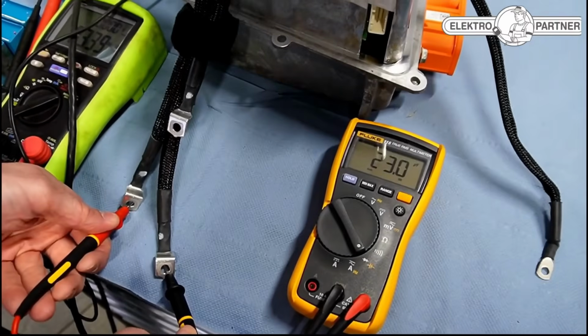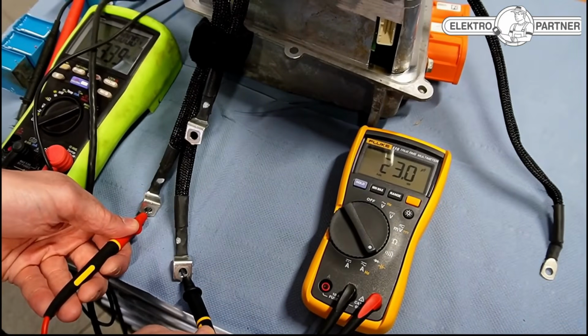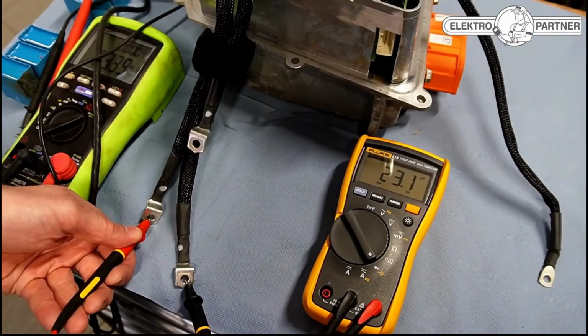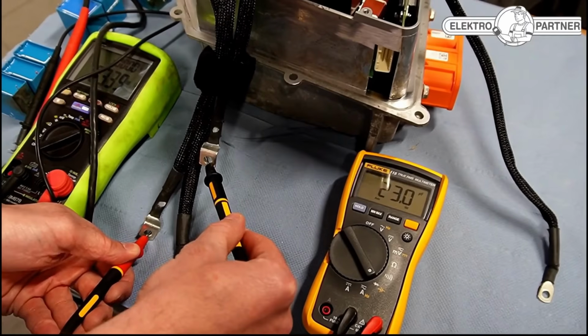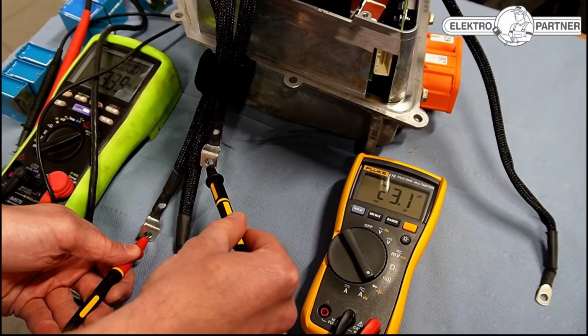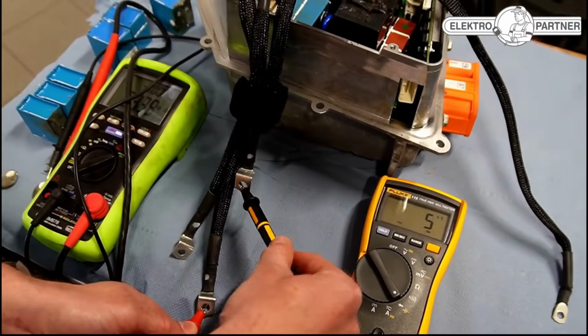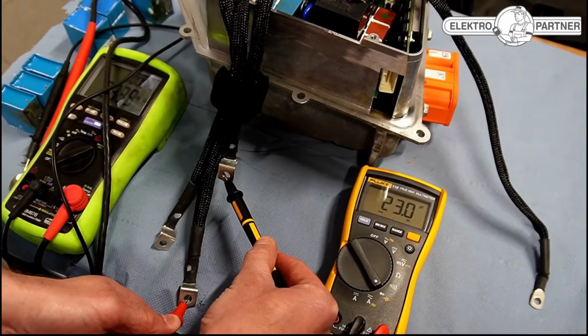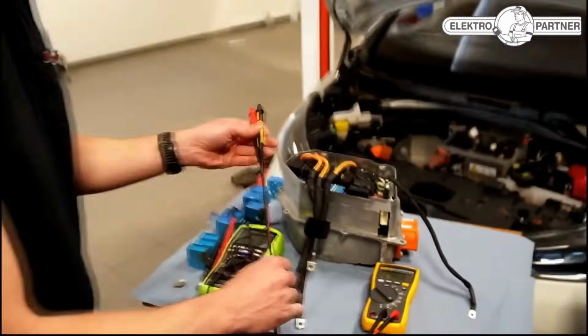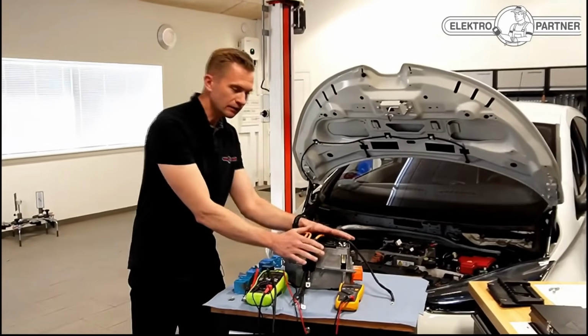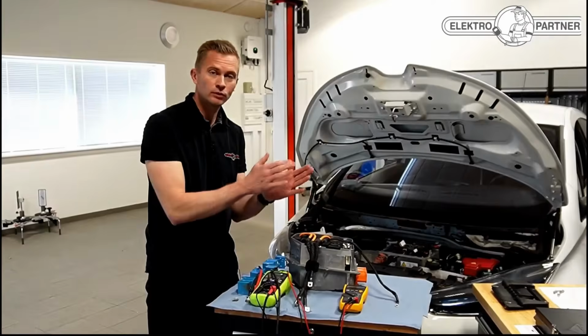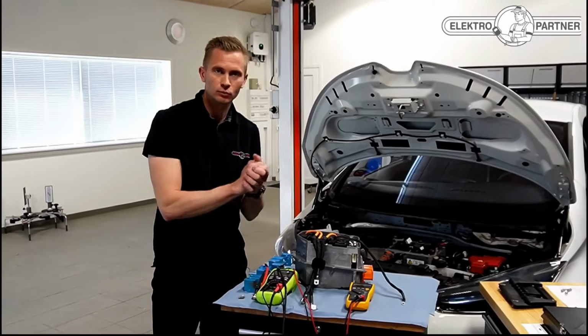Here we're measuring across the phases on this one: 23.0, 23.1 microfarads. Then we measure across the next one, also 23.1 microfarads, and the last measurement is also 23.1 microfarads. So all three measurements are now identical, which confirms we can do a before and after measurement we can use in our bulletin.